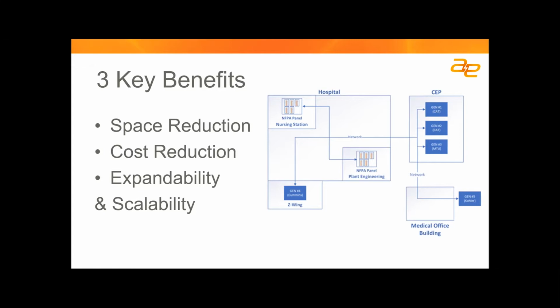In terms of the cost of implementation, with a multiple generator application, a typical generator has somewhere from 25 to 30 points. Depending on the type of installation, we've used anywhere from 50 points for just a 1 or 2 generator setup, up to 200 points. The biggest system we have is maybe a 1,000-point implementation. Those are all pretty cost effective compared to what it would cost to upgrade remote annunciators.